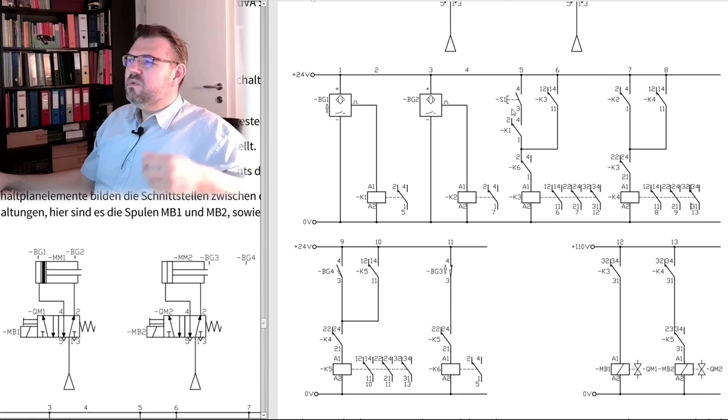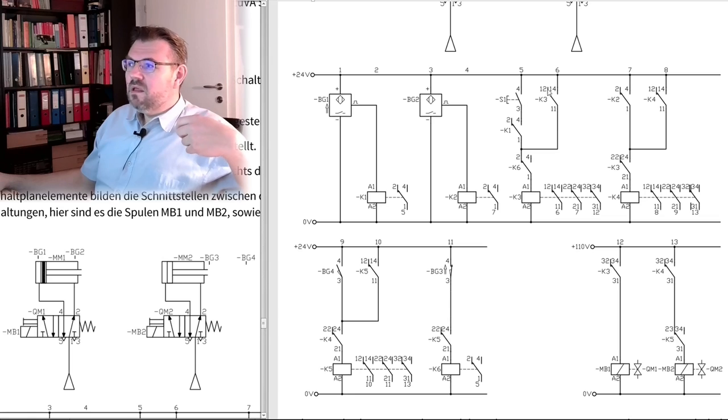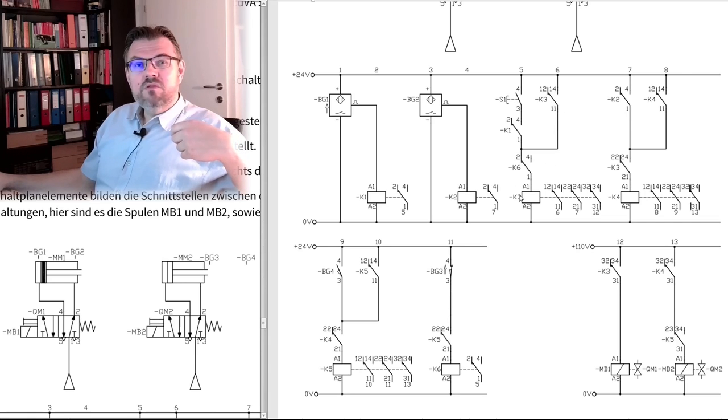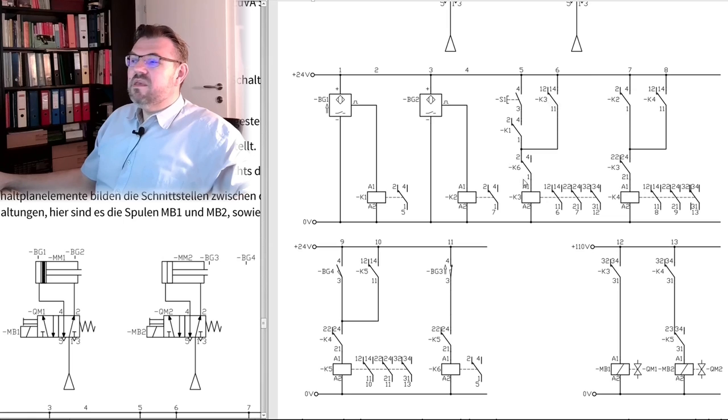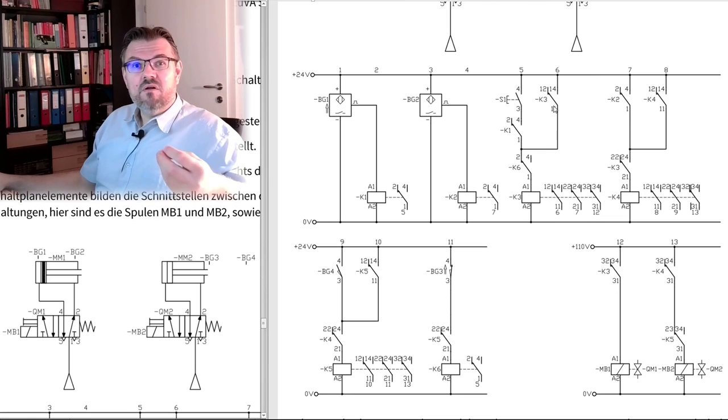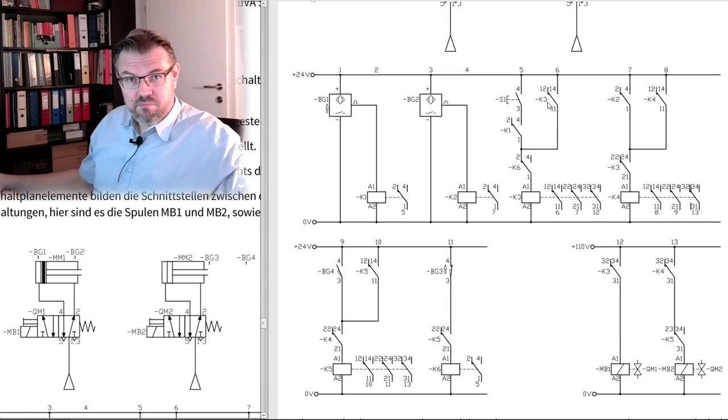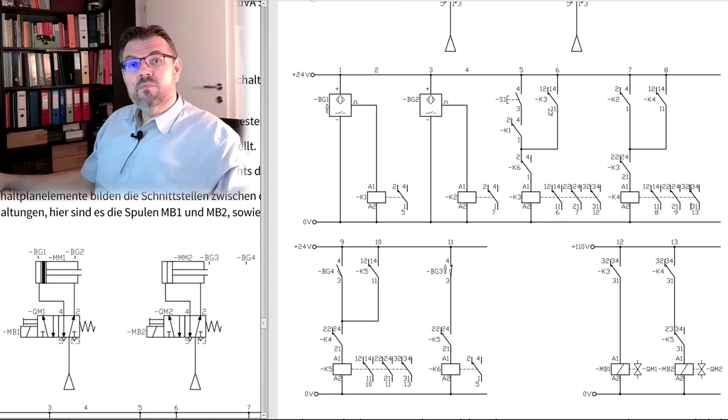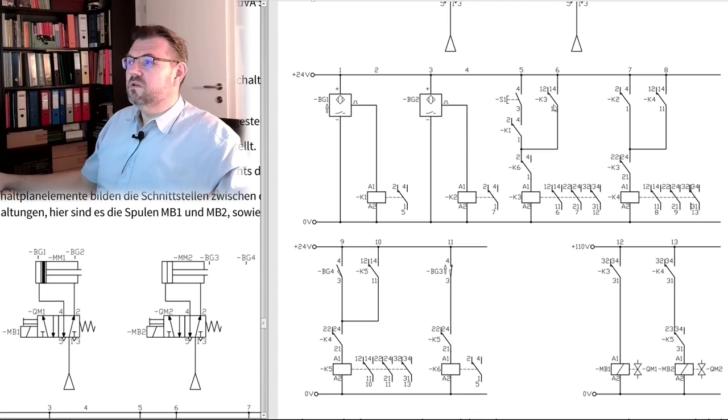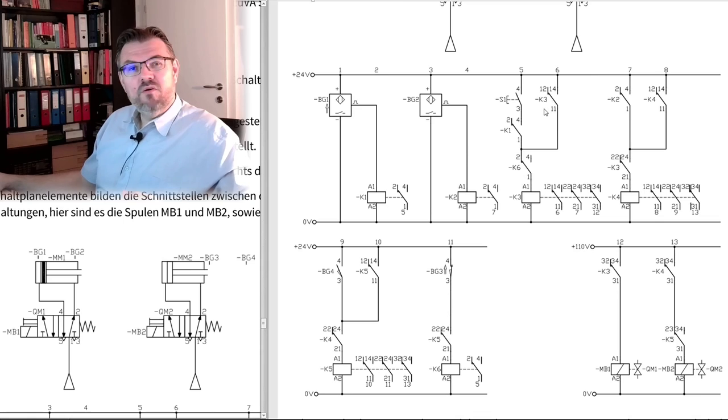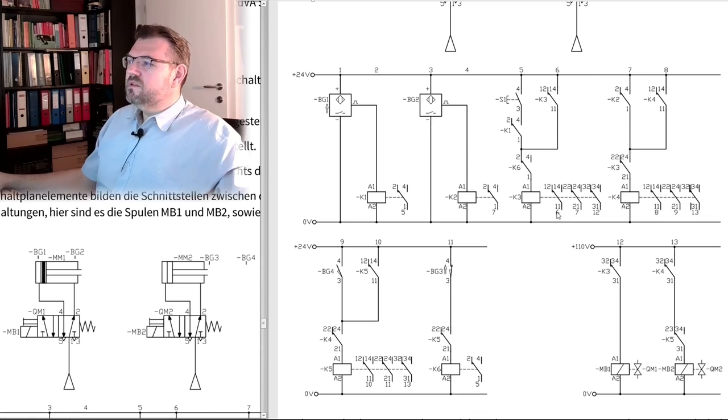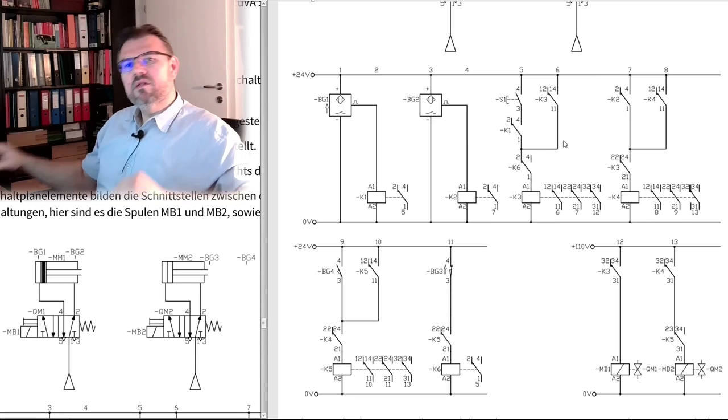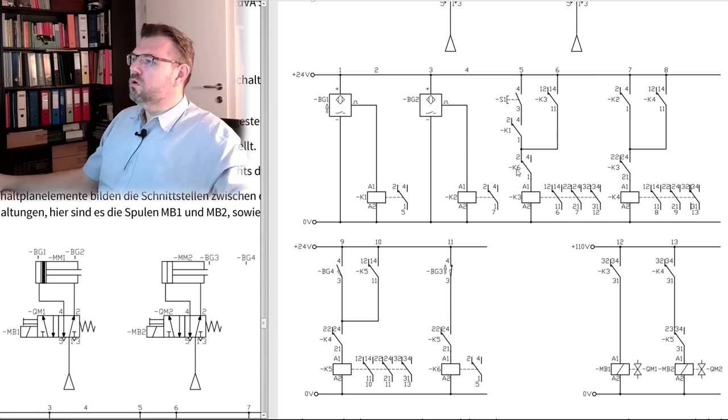In 6, K3 is activated, what does it mean? It means K3 is holding itself. This means, even if I release now the button, K3 will not be turned off, because one contact of K3 is giving itself a power. So, it turned itself on. It stored my button press. We've talked about this way of storing something back when we talked about electrical control. This is a self-holding contact. So, K3 is holding itself with this 6 contact. I can activate K3. K3 will stay on.